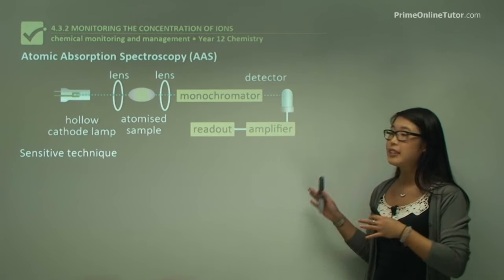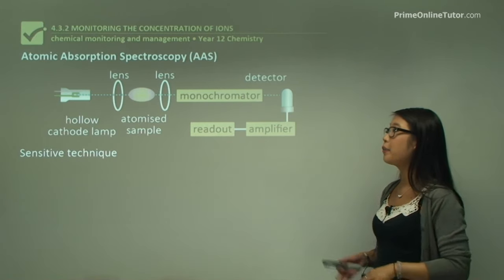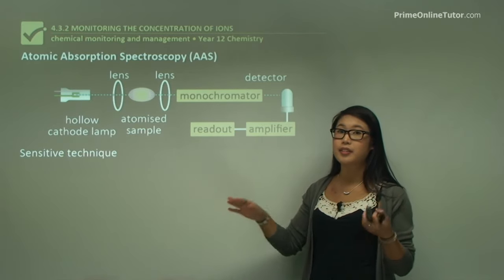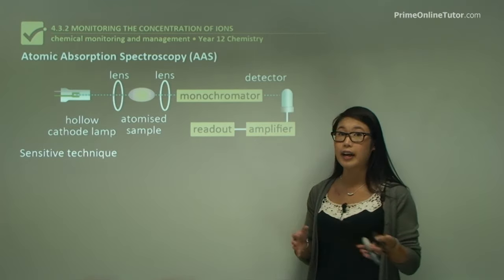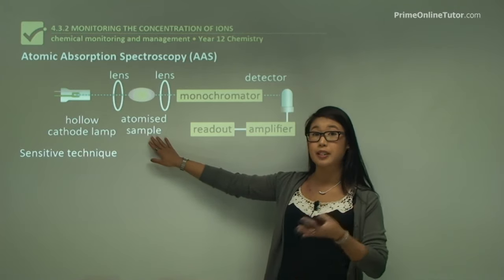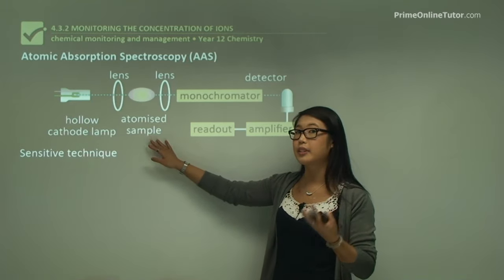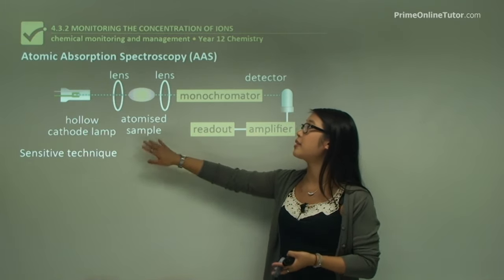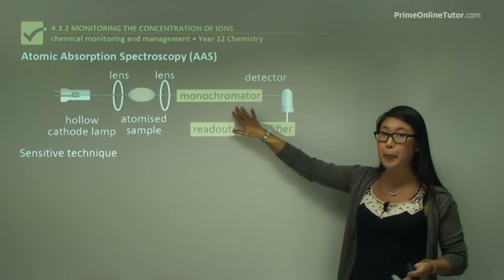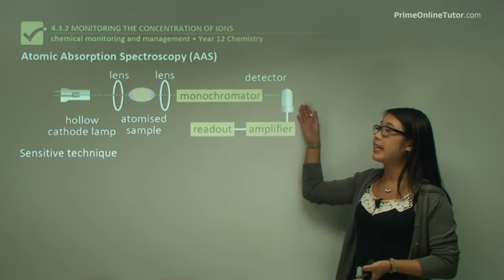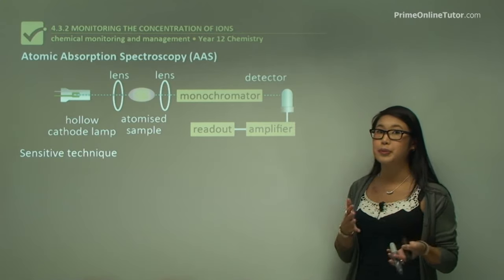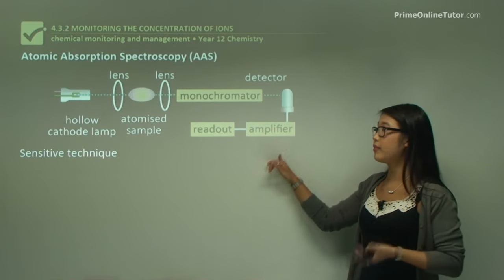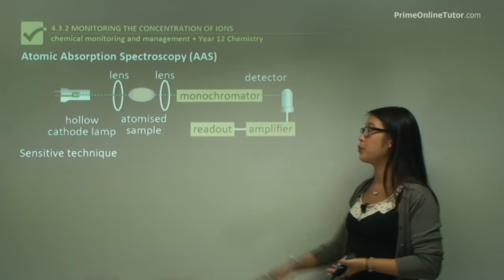This is a layout of how AAS works. First, a hollow cathode lamp is used to emit light, which is then passed through a sample. The sample has to be atomized because liquids and solids don't have light passed through them. Light passes through into the monochromator and is then detected with the detector. Usually the absorption is quite low, so we have to amplify the signal, and then we get the absorption as a readout.